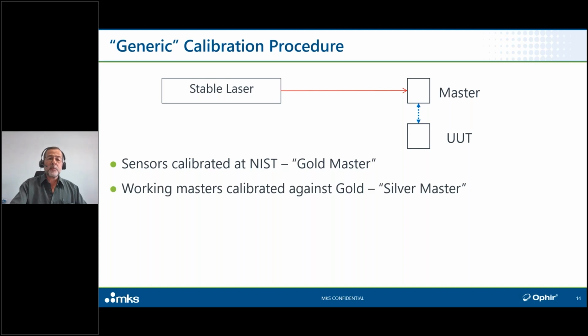Against the gold master, we calibrate silver masters, second generation. The gold masters then get locked away in a cabinet. And in our production, in our laser labs, we use on a day-to-day basis the silver masters. We periodically take the gold masters out of those cabinets and compare them to the silver masters, just to make sure that the silver masters haven't drifted for some reason over the course of that time.